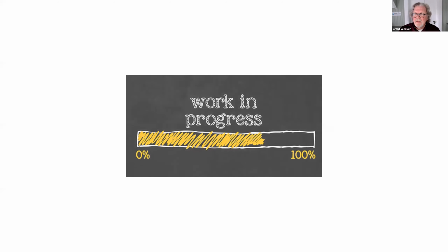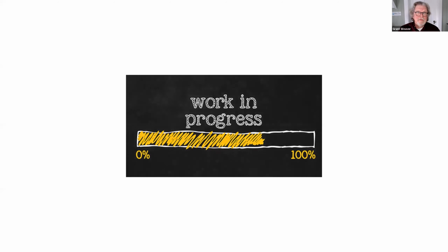The last session was oxidation ditches. I'm a little bit embarrassed to say that we've got a little bit of a work in progress, notwithstanding the fact that I've visited 150 treatment plants, and had the pleasure to work with the operators of most of them. The work on SBRs has been more recent. With oxidation ditches, I shared some numbers: oxidation ditches not designed for nitrogen removal, consistently getting 3 milligrams per liter or less.